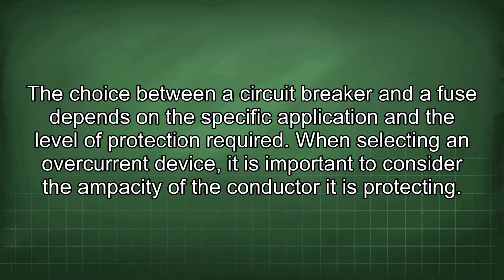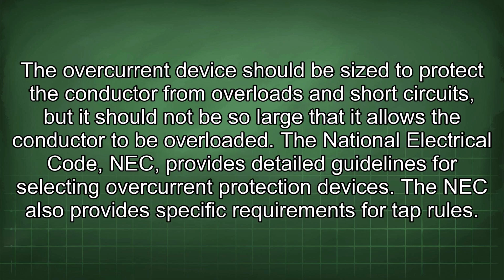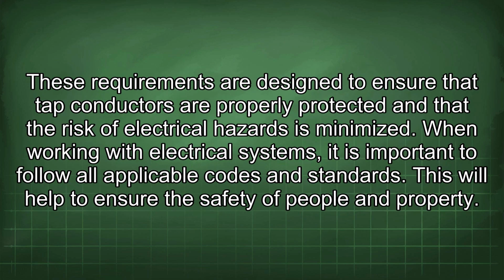When selecting an overcurrent device, it is important to consider the ampacity of the conductor it is protecting. The overcurrent device should be sized to protect the conductor from overloads and short circuits, but it should not be so large that it allows the conductor to be overloaded. The National Electrical Code, NEC, provides detailed guidelines for selecting overcurrent protection devices. The NEC also provides specific requirements for tap rules. These requirements are designed to ensure that tap conductors are properly protected and that the risk of electrical hazards is minimized. When working with electrical systems, it is important to follow all applicable codes and standards. This will help to ensure the safety of people and property.